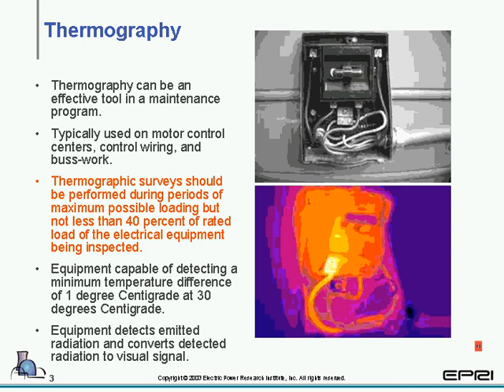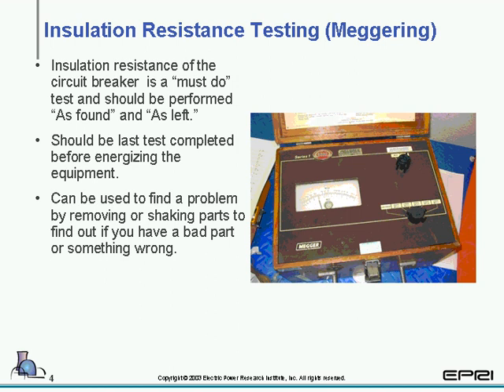The other comment I wanted to make was you should note that thermography cannot detect corona damage. There have been some cases where on medium voltage equipment thermography has been used effectively. There's been some type of bus problem or some type of overheating, and it heated the general area, and thus you could tell it even on the outside of the equipment, on the cabinets themselves. It can be done, but it cannot detect corona because corona does not develop that much heat.